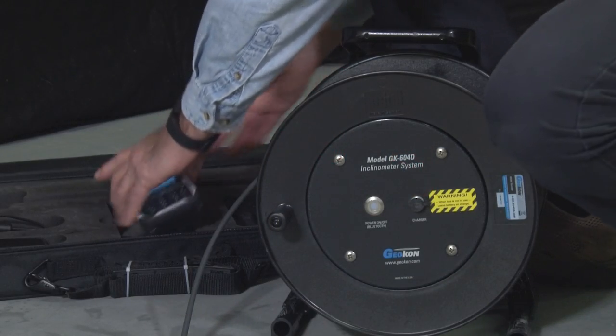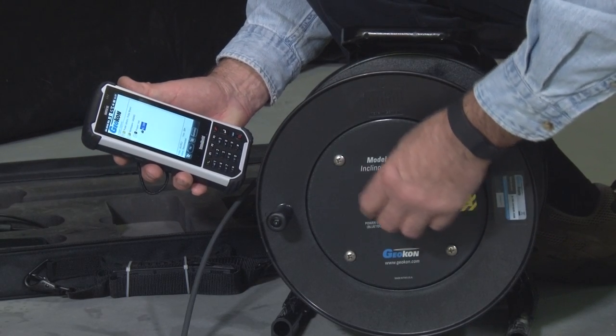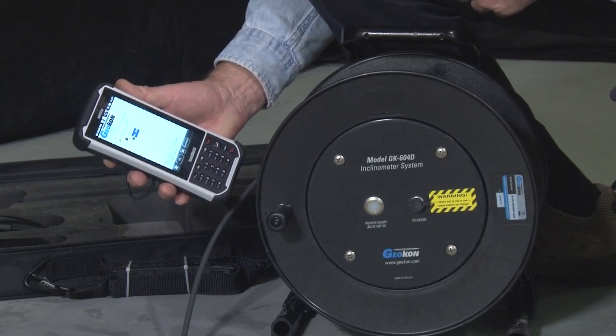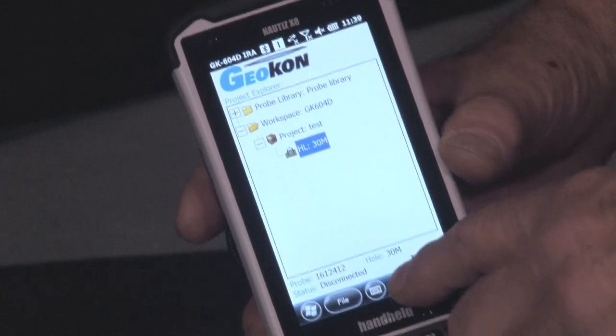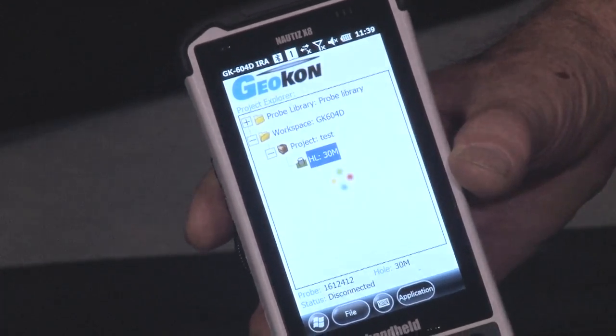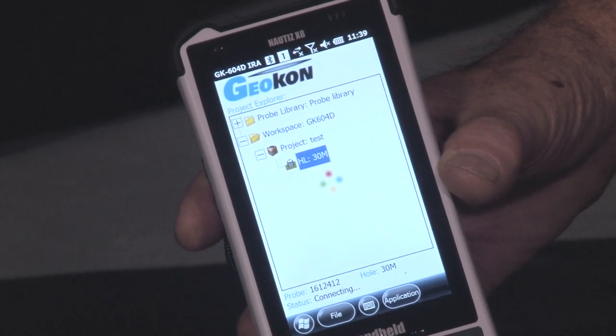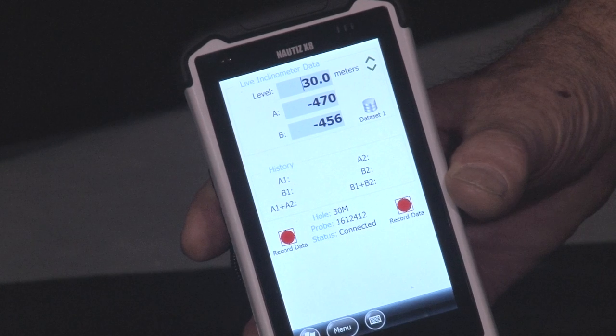With the handheld PC powered up, press the Bluetooth Connect button on the reel to establish wireless communication. The blue light will flash. On the field PC, press Application, then Live Readings from the pop-up menu. The field PC will indicate when connection is made.